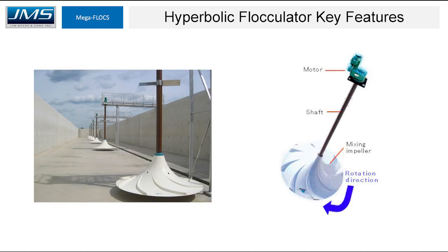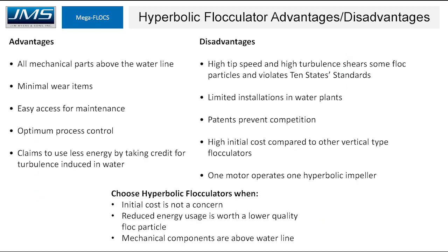Hyperbolic flocculators have a distinct design at the bottom with a shaft into a gearbox that accommodates all axial and radial forces. These flocculators create a specific type of turbulence in the basin. Manufacturers take credit for the drag coefficient and the relative velocity of all the turbulence created. Some advantages are that all mechanical parts are above the waterline, minimal wear items, easy access for maintenance, and optimum process control because each drive speed can be adjusted. There are also some claims of lower energy use.